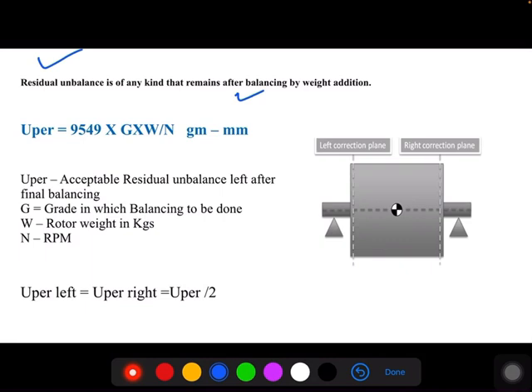The formula used for the residual unbalance as per the standard 1940 is: U_per = 9549 × G × W / N. U_per means acceptable residual unbalance left after final balancing. This is the formula to calculate the residual unbalance for different quality grades.